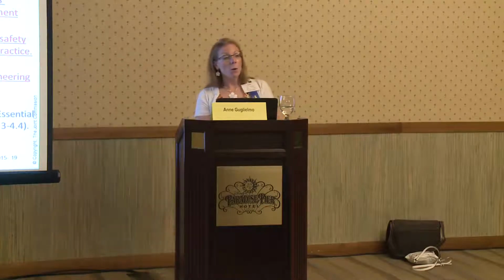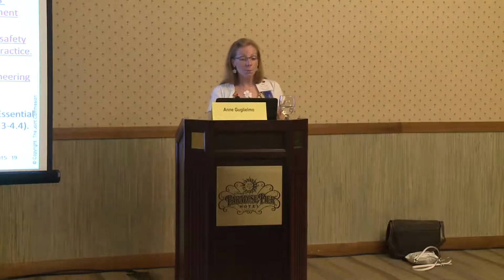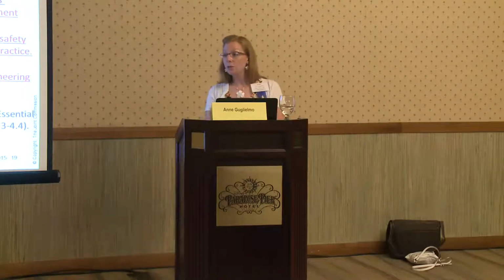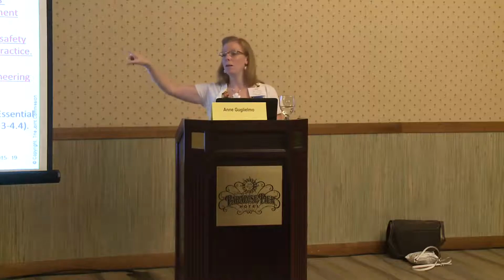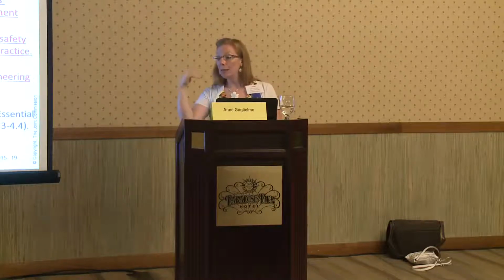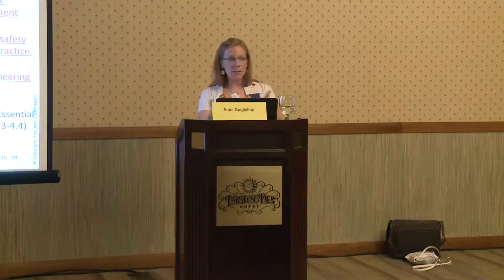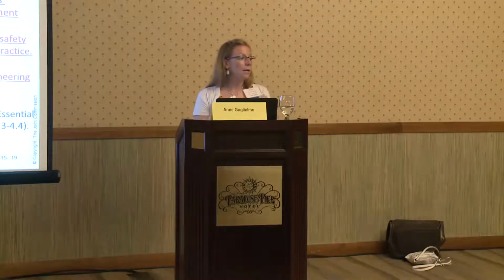The AEM, of course, cannot reduce the safety of the equipment, and it has to be based on a standard of practice. So if you're going to do this, we can't just say, you know what, we don't like this manufacturer, we don't want to listen to him, we're going to go a different route. We want to make sure that that different route is founded in a national standard of practice, or that you're making that decision for good, solid reasoning.